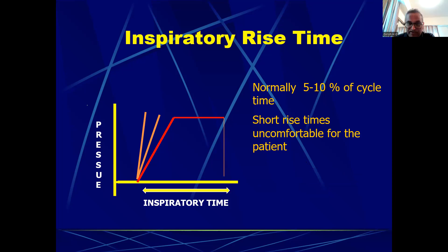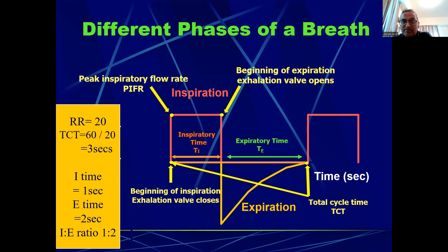If I say that 10% of the cycle time will be inspiratory rise time, that means in this particular example, for 3 seconds, I put 10% as an inspiratory rise time. Whatever pressure I set will be reached in 0.3 seconds, and for the rest of the time, it will be staying there. I think I made myself clear. So this is inspiratory time, whereas this is inspiratory rise time. That means how fast it reaches the level, and then it stays there like this.